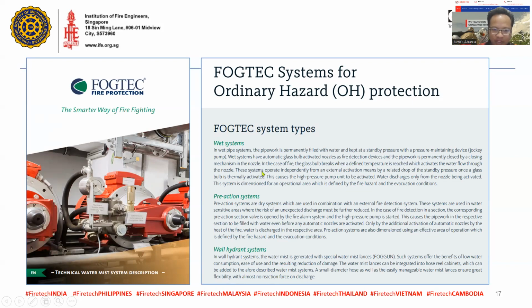So that is a wet system. Another type is also a pre-action system. Water mist can also be applied as a pre-action system. As you all know, a pre-action system is a combination of dry and wet. Upstream of your pump it is wet and downstream it is dry because it's a nozzle. Once the detection activates that there is fire, it will open the solenoid valve, thereby opening your water mist section valve. It will discharge the mist of water.